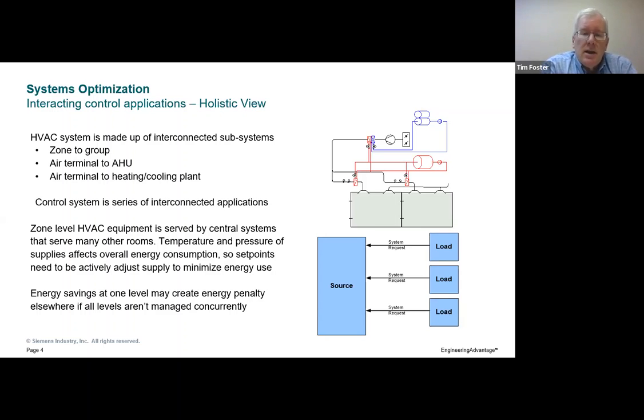And as the chart indicates, all of those decisions should start with the load, and load we would define as the actual space and the people in the space. So if we use that to reset our building strategies for air handlers and central plants, we can gain a lot of energy efficiency and still make sure we maintain adequate space conditions. So that would be one. The second one, Tom, if you could advance.